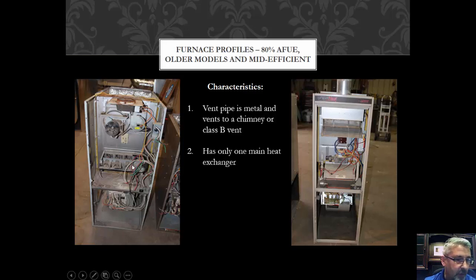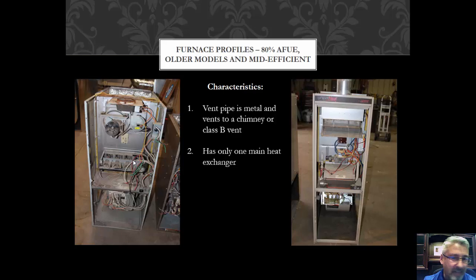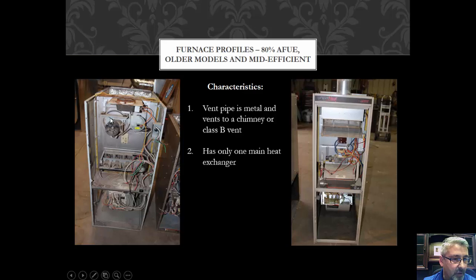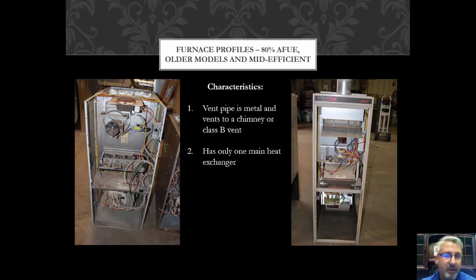If you look at this furnace, you've got four in-shot burners, meaning four cells, but still one primary — no secondary. This Lennox has a draft door actuator that closes on an off cycle so you don't have a constant draft up the chimney. This one is atmospherically vented — it just goes up to the B vent or chimney. The other one has a vent motor that pushes the flue gas into a chimney or B vent. 80% furnaces are not designed to vent outside on the exterior without modifications.